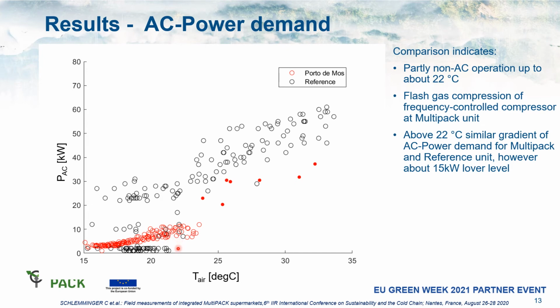while at temperatures above 22 degrees C, we see an increase of AC load both on the MultiPACK side as well as on the reference side. However, the trend is comparable, but the absolute value is about 15 kilowatt lower for the MultiPACK side than the reference shop.